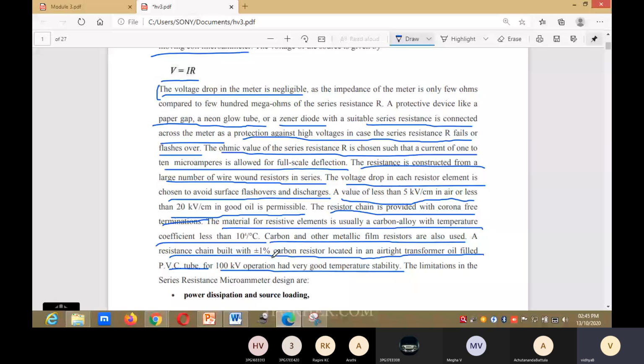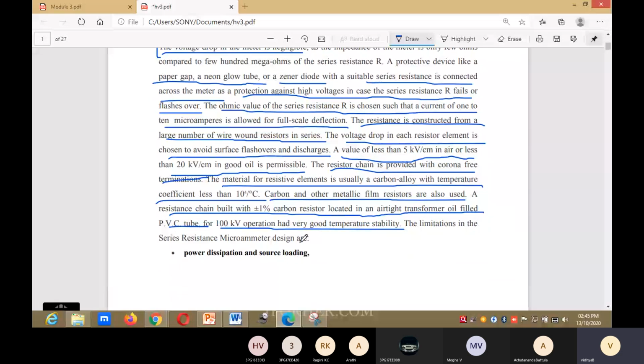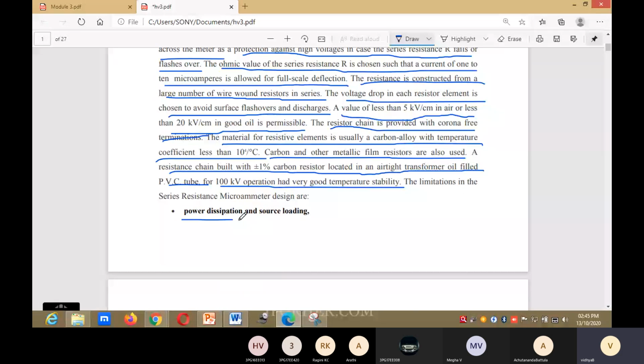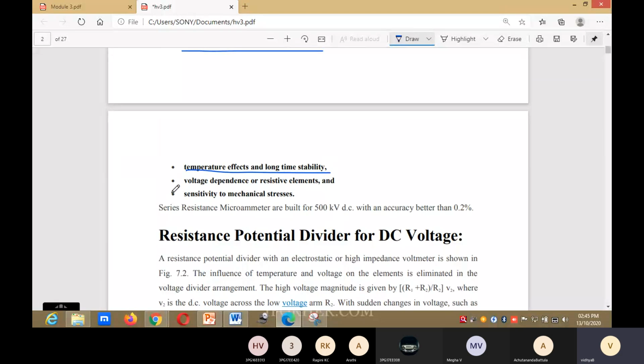The limitations in the series resistance microammeter design are power dissipation and source loading, temperature effects and long time stability, voltage dependence of resistive elements, and sensitivity to mechanical stress. Series resistance microammeters are built for up to 500 kV DC with an accuracy better than 0.2%. This is the series resistance microammeter.